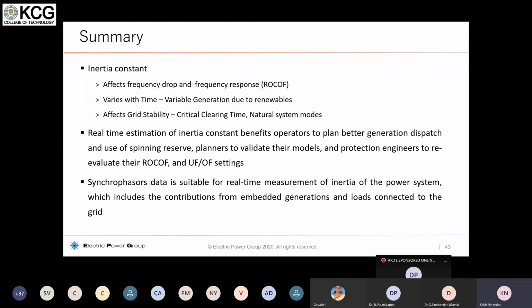In summary, the inertia constant affects the frequency drop in the frequency response. As I said, the effective inertia varies with time, and it affects grid stability, critical clearing time, and natural system modes. Real-time estimation of the inertia constant helps operators plan better generation dispatch and use spinning reserves, and helps protection engineers evaluate ROCOF and under-frequency and over-frequency settings and so on. And synchrophasor data is suitable for real-time measurement of inertia for a power system, which includes the contributions of embedded generation, loads connected to the system, renewables, etc.